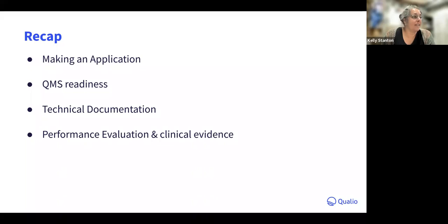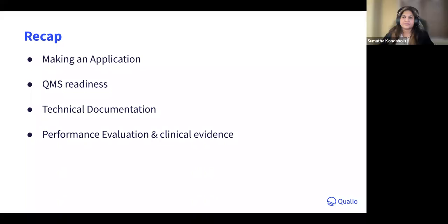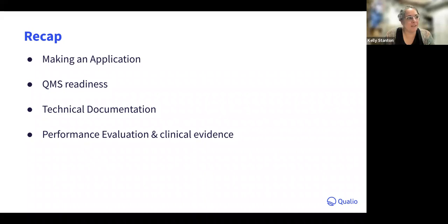Your technical documentation for your product needs to align to those requirements. You are an in vitro diagnostic device, but you're also a medical device. So you want to make sure that your tech files meet those requirements. And then your performance evaluation and clinical evidence. As I alluded to earlier, especially if you haven't had to do this before, you probably have some of this information, whether it's in your marketing information or that kind of information gathering. That's all valid data to use in these situations. You want to make sure that you're gathering that in a systematic way under the elements required for good document control, etc.